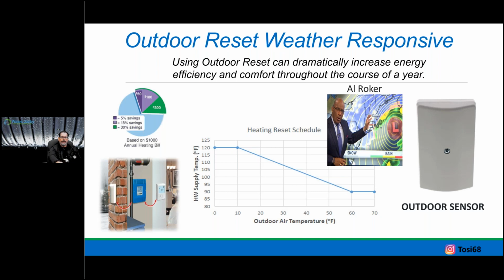And now it goes, okay, hey, it's not 0 out. I don't need 180. It's something warmer out. I only need 150-degree water, not 180. So I'm not having to keep firing and losing and not taking advantage of the fuel being spent. And also, going back to a warmer day, oversized emitters pegging 180 or higher, you're now creating maybe an uncomfortable condition as well.